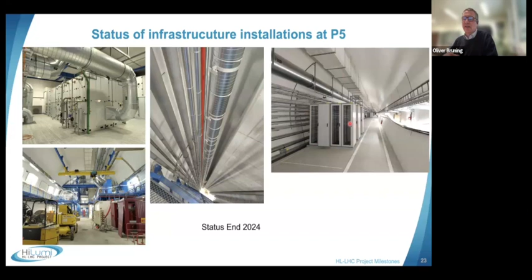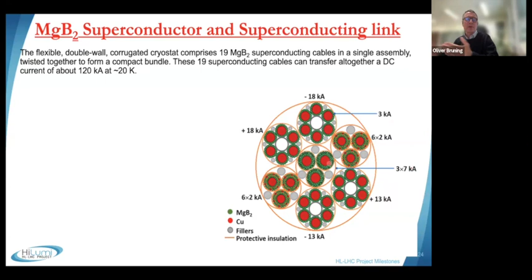A picture of the superconducting link, the magnesium diboride superconductor, and this is a cross section of what it looks like. In red is mainly the copper cable that gives the mechanical structure and stability. The actual superconductor is the small green dots. Here's an assembly of 19 cables with various current ratings, up to 18 kiloamperes, some 6 kiloamperes and some 13 kiloamperes. The whole cable in total can transport over 100 kiloamperes when fully powered.